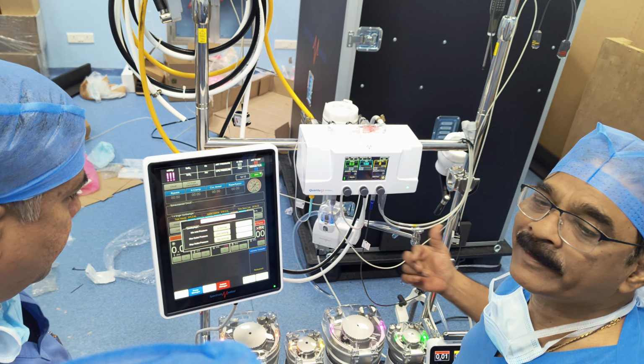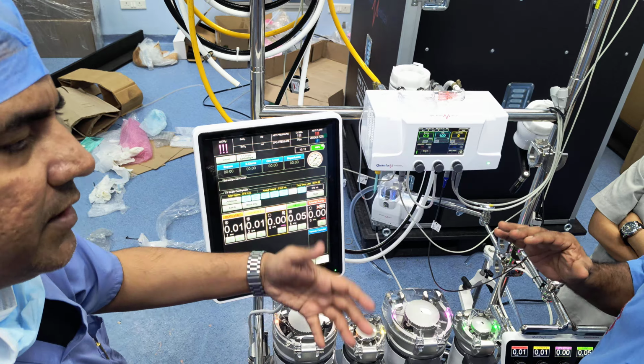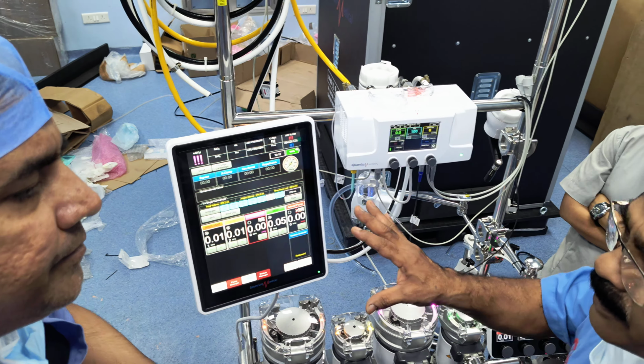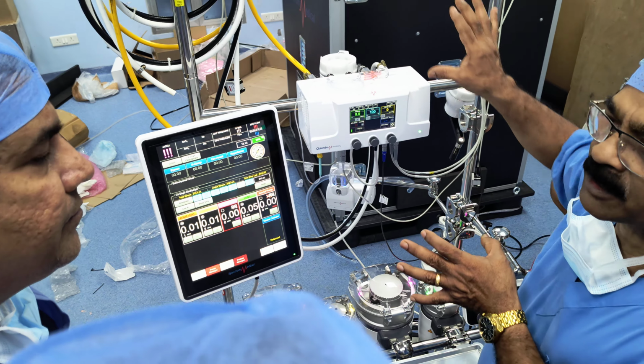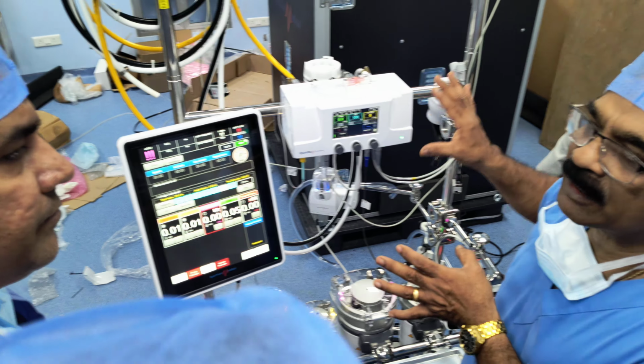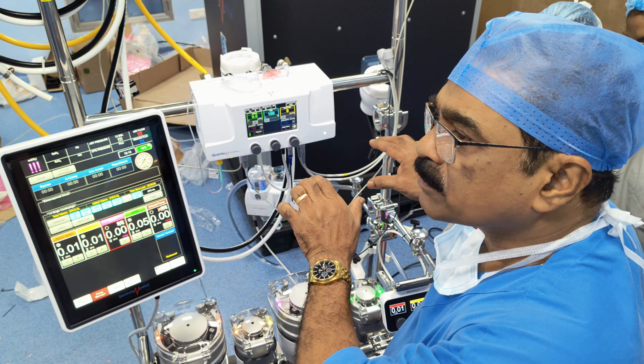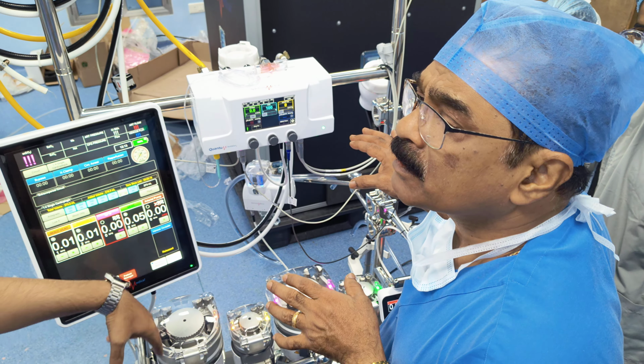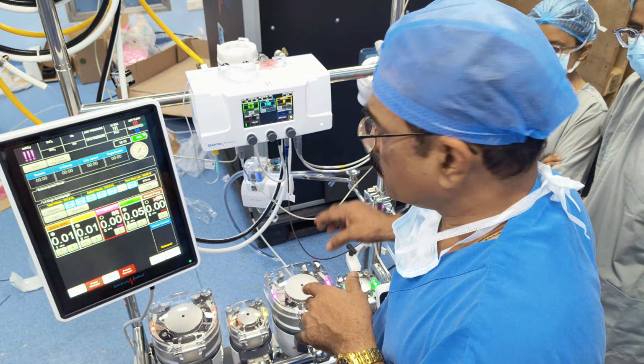How did you come up with this, that we have to keep the 5 mm of pressure? Did you go with research or something like that? No, it is an indication that there is a positive pressure in the line. Which line? Arterial line. See, your cardioplegia pump is sucking from the arterial line. You have the occlusion pump also there. You are going through the occlusion pump to the cardioplegia pump, right? So the inlet pressure, that's why I'm saying cardioplegia inlet pressure. What about this pump?